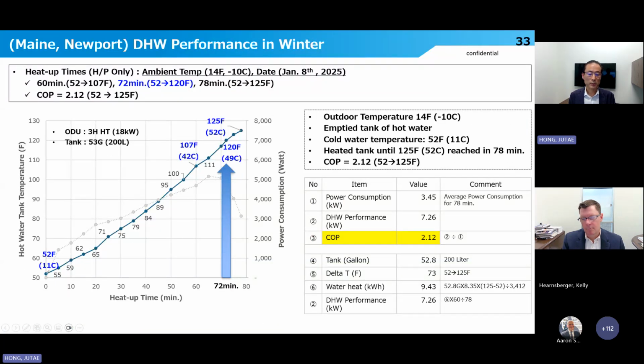Domestic hot water performance in winter. We filled up the tank with tap water at 52 degrees and heated up the 50-gallon tank with heat pump operation only in January this year. It takes 72 minutes to heat up the tank with 120-degree hot water at 14-degree ambient temperature. The average COP was 2.12 to heat up the 50-gallon tank from 52 to 125.